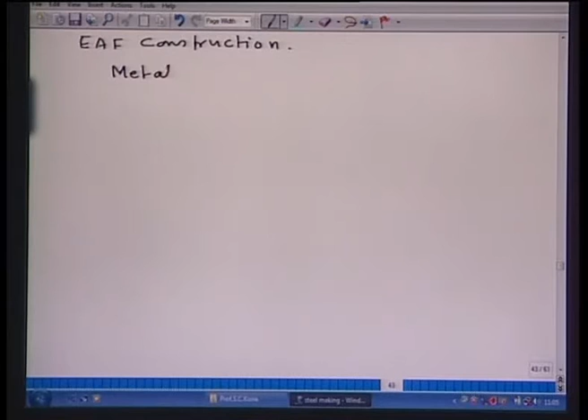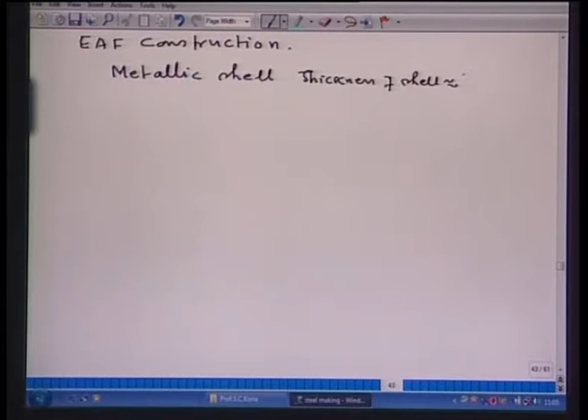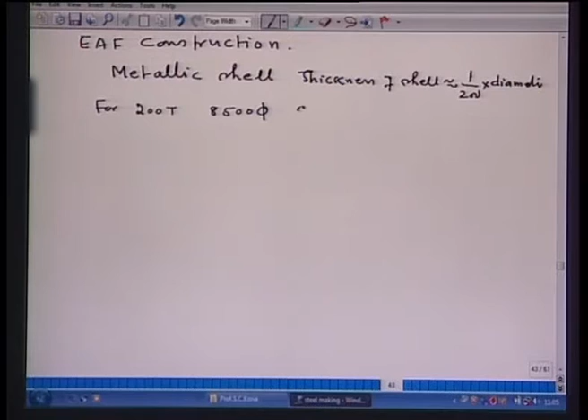Of course, metallic shell, and the thickness of the shell is approximately 1 by 200 times the diameter of the furnace. So, for example, if we have a 200 ton electric furnace, 8500 is the diameter of the shell, then the shell thickness is around 45 millimeter.